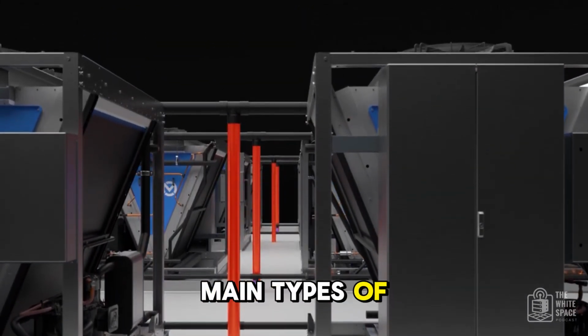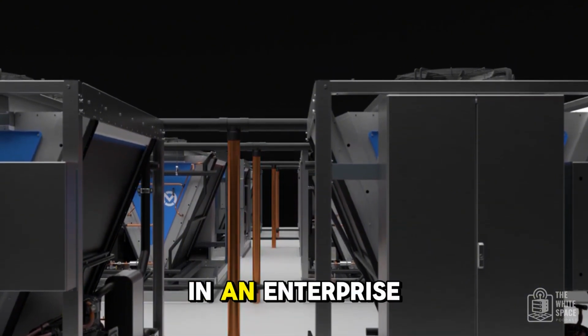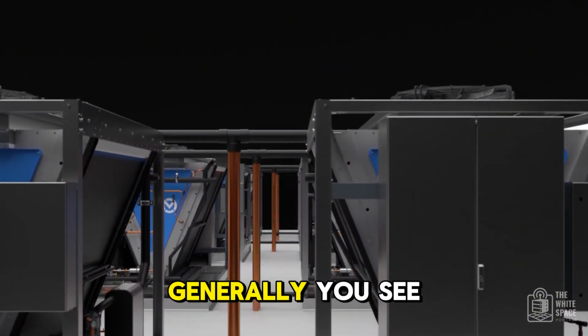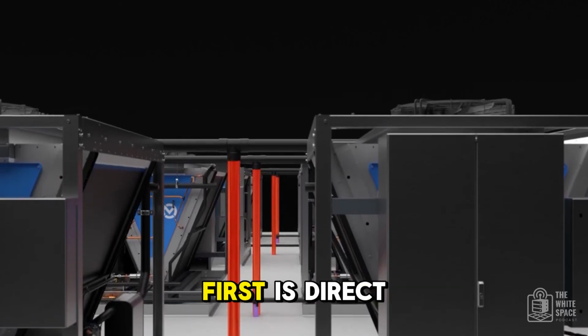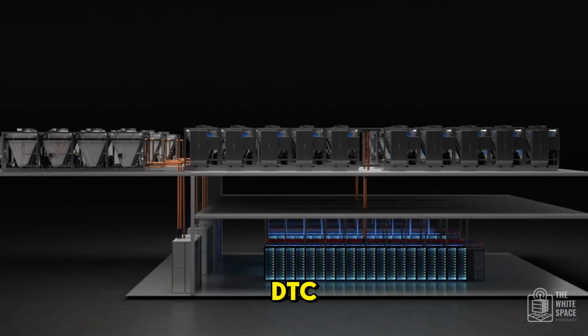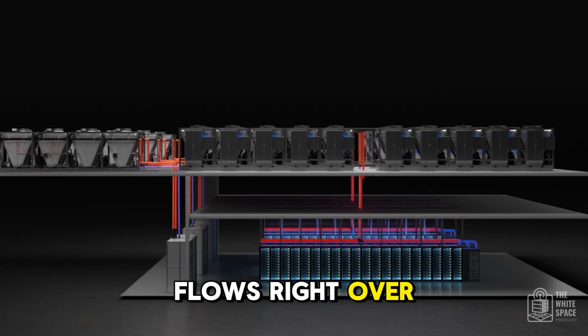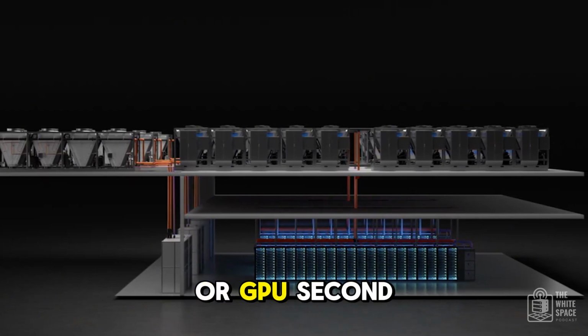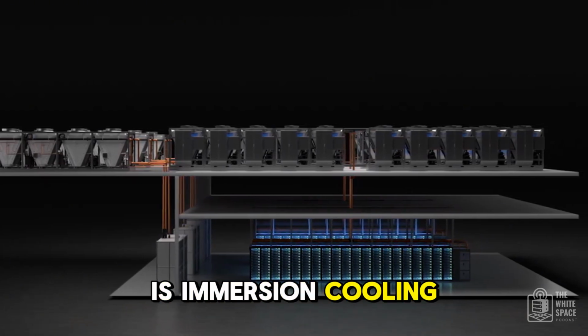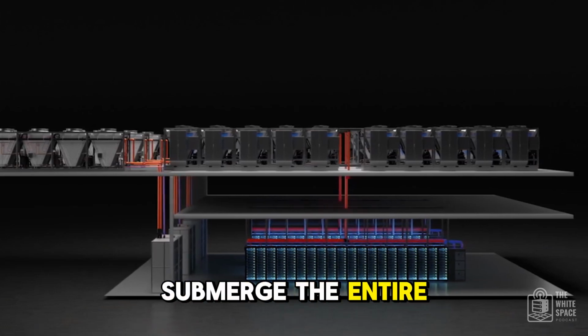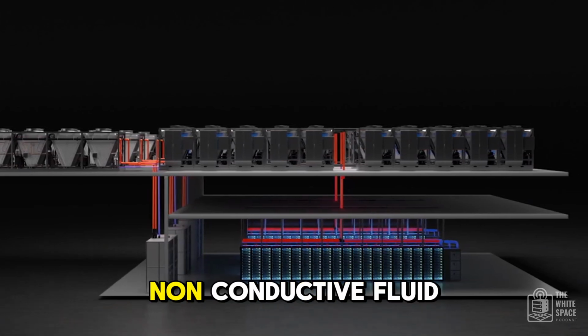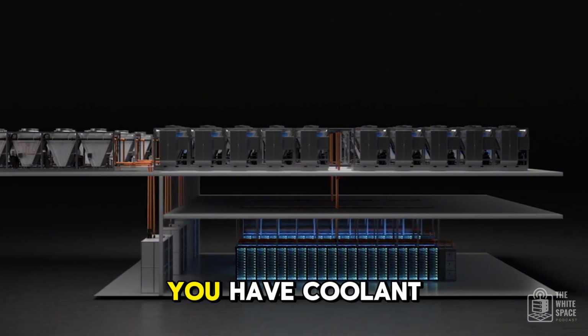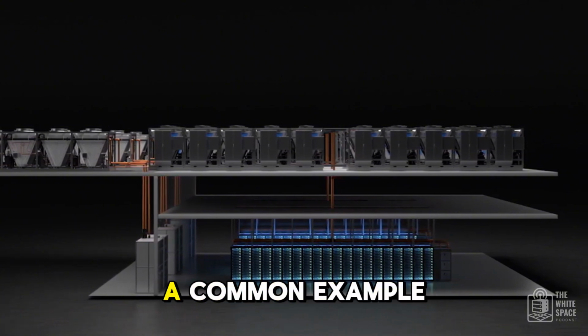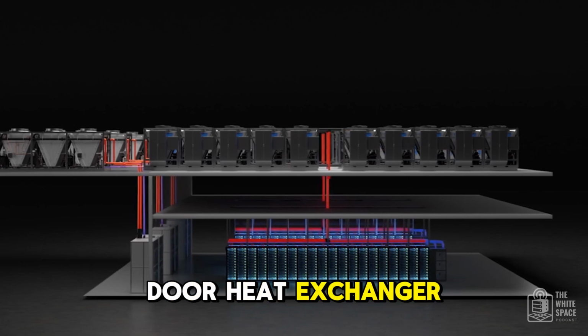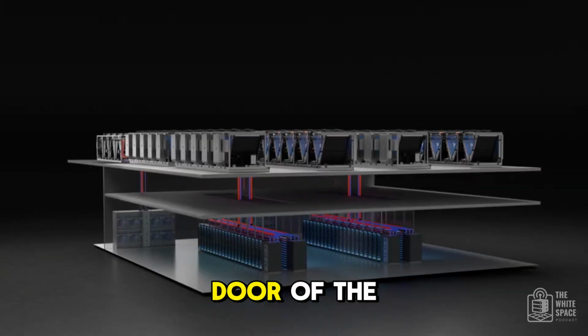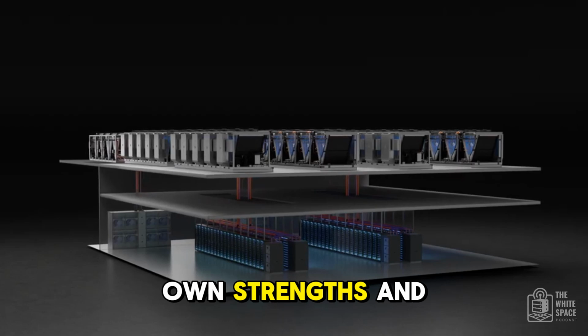Okay, so we see the general benefits. What are the main types of liquid cooling we'd actually find in an enterprise data center today? Generally, you see three main approaches. First is direct-to-chip, or DTC, where liquid flows right over the hottest parts, like the CPU or GPU. Second is immersion cooling, where you literally submerge the entire server or component in a special non-conductive fluid. And third, you have coolant circulation systems. A common example is the rear door heat exchanger, where liquid circulates through the back door of the rack itself. Each has its own strengths and weaknesses.